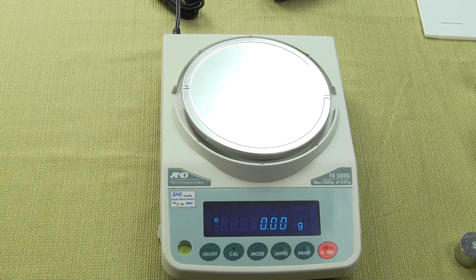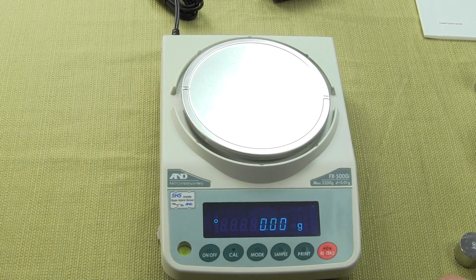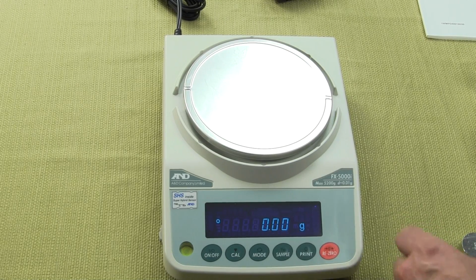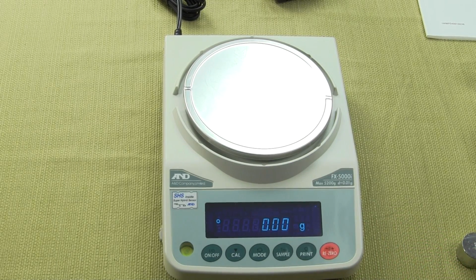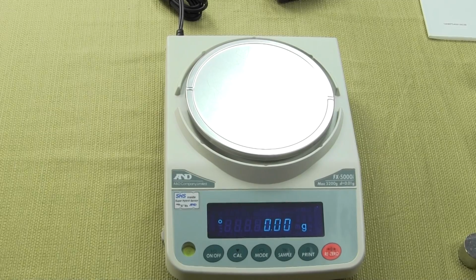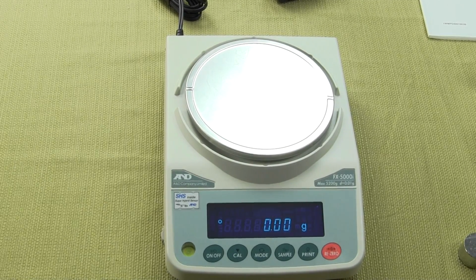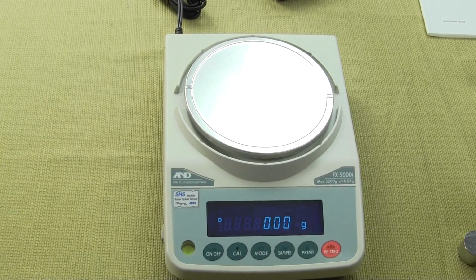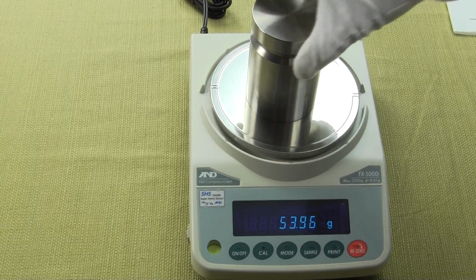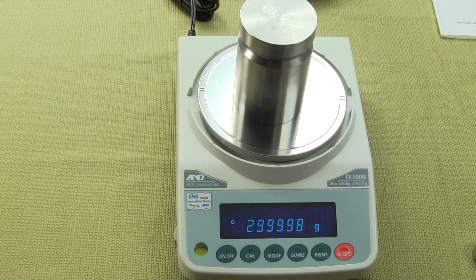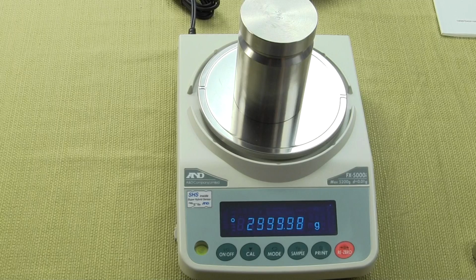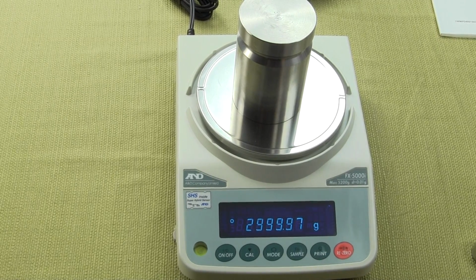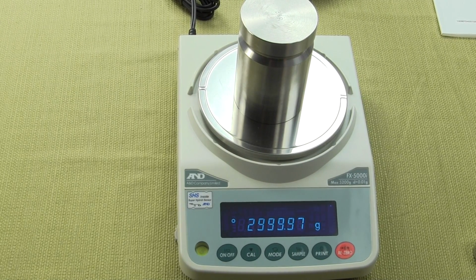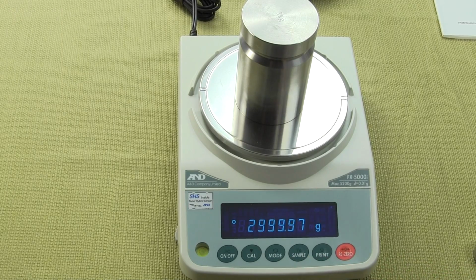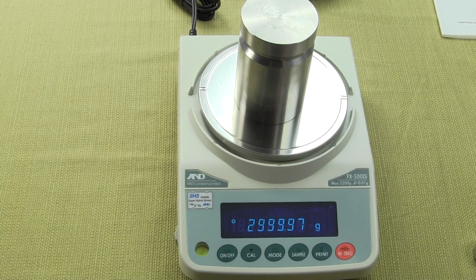You have the parts counting feature. If you ever want to count any pieces or parts, the presets for the parts counting are 5, 10, 25, 50. You have the ability to change the response time. I wanted to show you that. So if we have a weight on here, you can change the response time, and what the response time does is it allows the stabilization time to show the weight, depending upon if you have some air current.